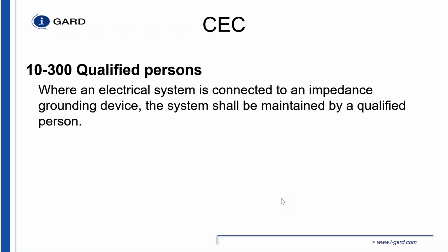Obviously that goes without saying, and I don't understand why it particularly pertains to this clause here, because I think all people that work on electrical systems should be qualified. And so I don't understand why special attention is needed here, other than that when you have a ground fault on an impedance grounding device, if you're going to measure the voltages in Z462 to recognize the state of de-energization, you're going to measure phase to phase and phase to ground.